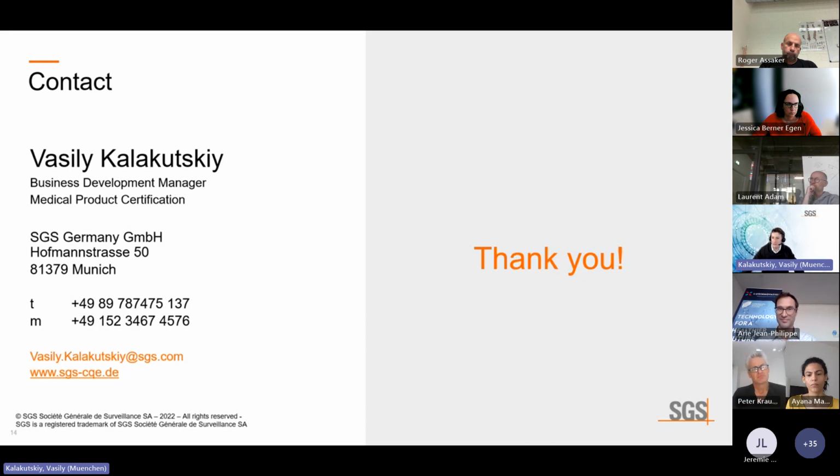and then the calculation of time is done based on the MD9 document. I will put the IAF MD9 in the chat, so you can see it. This is almost the main thing: how we calculate the length of the audit. It depends upon the size of the company, and on top of that we add add-ons for the assessment of the technical documentation and the special items of the MDR quality management system. So you can estimate how many employees your company has and apply some factor, so to speak.